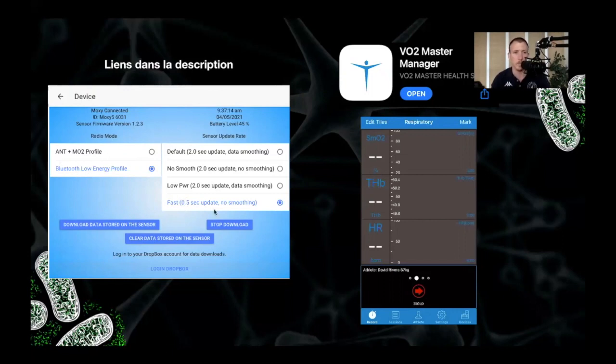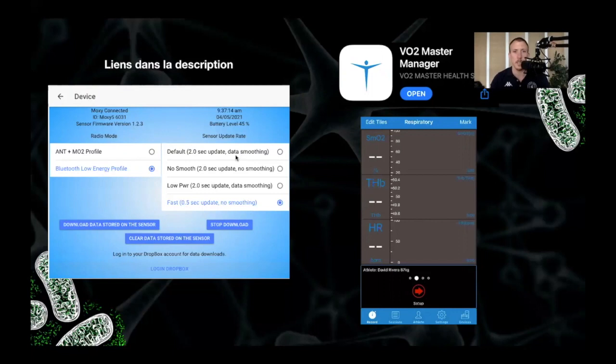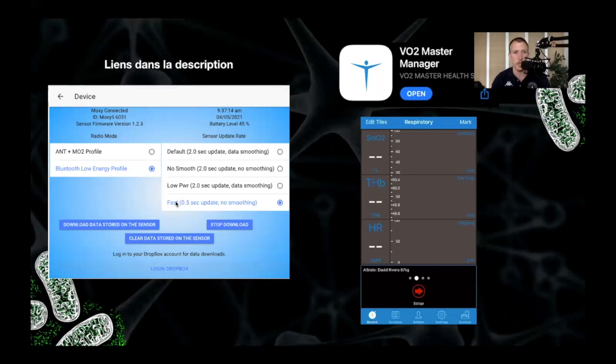I like to set it up to the fast updates rates. So it's a 0.5 second update with no data smoothing. The two second, the default setting is a two second update with about a 10 second data smoothing. So it's good for longer stuff, but if you're doing short intervals, you might miss some data points. So I always leave my Moxies on the fast update rates.